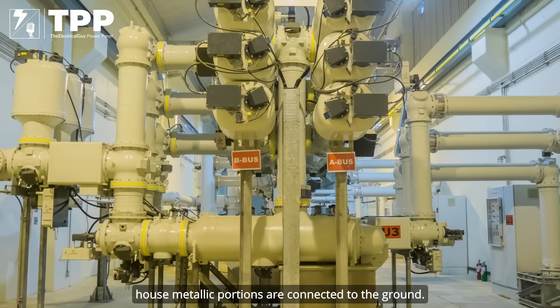So two examples. First, like I said, for the AIS it is pretty simple. I would not say simple, but more of a generic understanding of how the ground grid is, because there is no building in it. I mean, we do have the control house for the relay and the panels, but those control house metallic portions are connected to the ground. What happens is GIS is usually within a building that is enclosed. Based on that, it could have a multi-layer arrangement, meaning first layer within the ground, first layer at the ground floor, second floor could be elevated for the breakers, and third may be transformers, and vice versa.